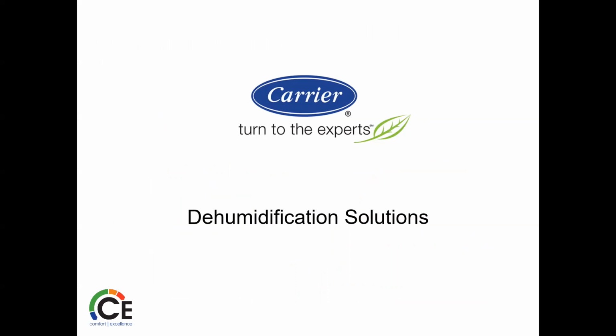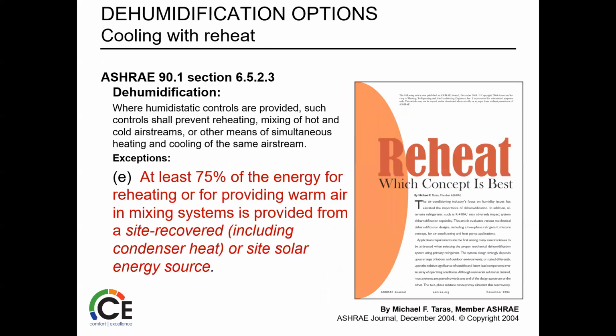So what do we do? This is part of that document I showed you. 75% of the energy for reheating or providing warm air in mixed systems is provided from a site-recovered condenser heat or solar heat source. So true dehumidification is coming from something else. Hot gas reheat is what we're going to talk about here in a little bit. And this is a way to increase and make dehumidifying more efficient.